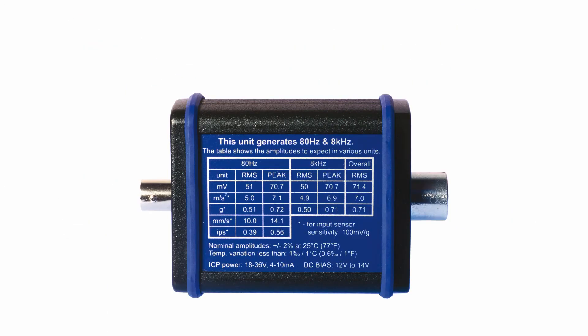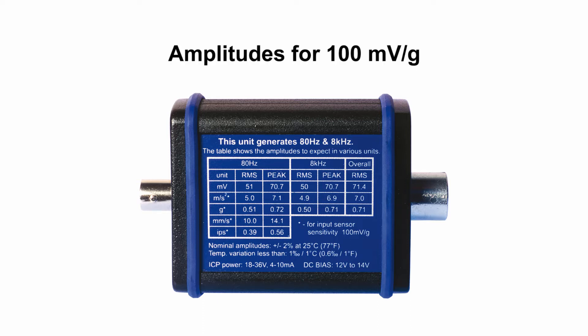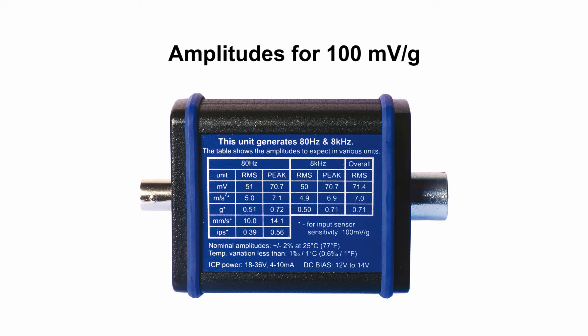The Sensor Simulator generates stable voltage signal on 80 Hz and 8 kHz and if you set 100 mV per G sensitivity into your vibration meter or analyzer, you should see similar values as per table which is written on the Sensor Simulator.